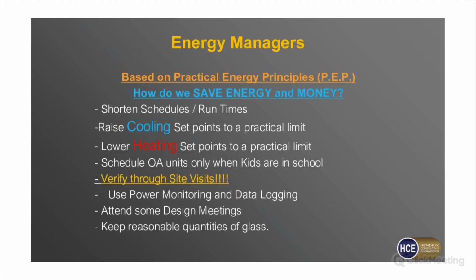On the energy manager side, you're going to be watching the schedules, trying to keep those schedules as short as possible, along with the run times. They're always going to be trying to raise cooling set points as high as they can and lower heating set points as much as they can. But we know they can only be raised and lowered to a point, otherwise people will cheat and find a way around them. They'll put light bulbs or little heaters or coffee pots near the thermostat to trick it. It becomes really important that everything is calibrated, so if 74 is our cooling set point, we're actually giving them 74 and it's not out of calibration where they only get 78. You don't want to put people in that position.